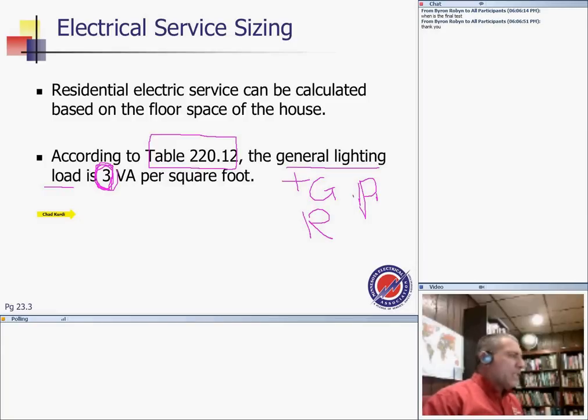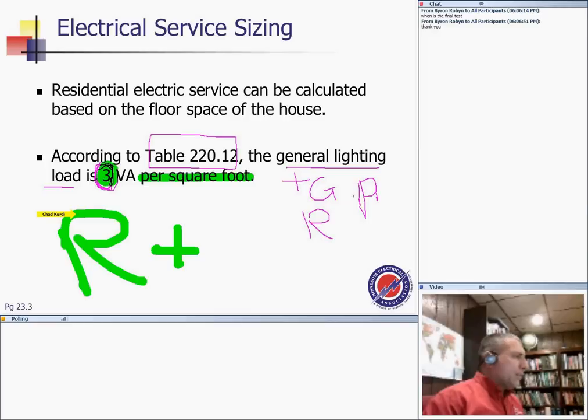have volt amp that's just lights only. For residential, and I can't emphasize this, it confuses the people all the time. When you do calculation based on the 3 volt amp per square foot, this includes receptacles, general receptacles, as well as general lights. Fully residential. If it's commercial industrial, it only includes lights. Anything guys about this? Very important to understand that general purpose receptacles are included in this 3 volt amp. Any questions?